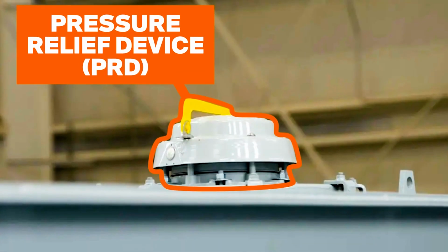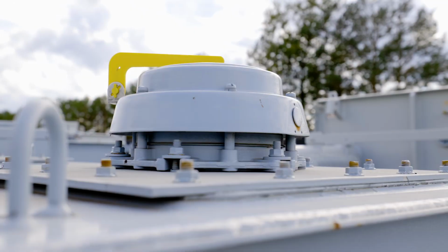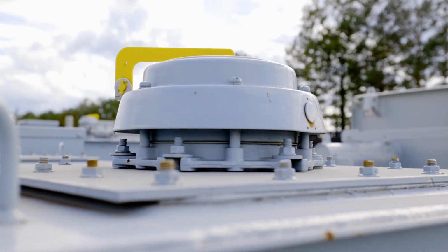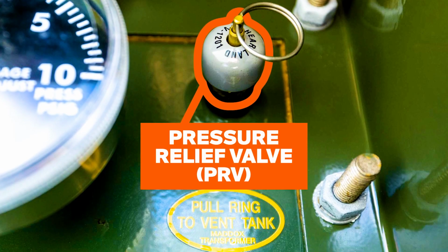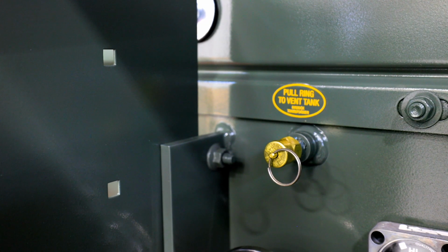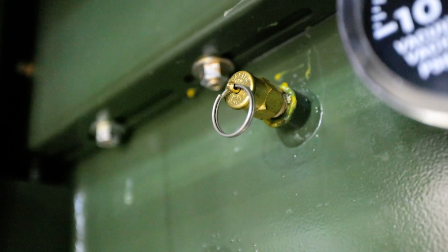A pressure relief device, or PRD, is a type of valve on a sealed transformer tank design that relieves excess tank pressure that might have built up due to an internal fault or overheating. To prevent the tank from deforming or rupturing, the PRD vents the excess pressure from the transformer tank before it reaches a critical level. Most liquid-filled transformers are outfitted with a pressure relief valve, or a PRV, which allows the headspace to vent excess pressure. This PRV is typically set at about 5 pounds, so at about 5 pounds of pressure, that pop-off valve will unseat slightly to let the excess pressure off, and then it'll reseal back to seal the tank.